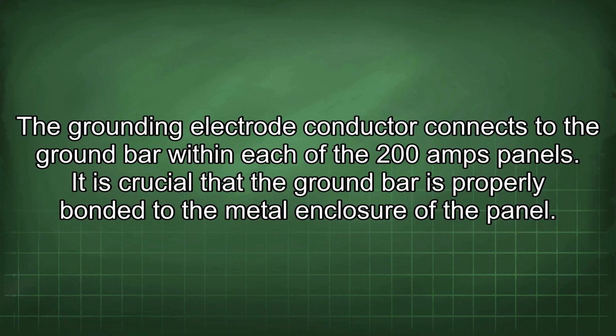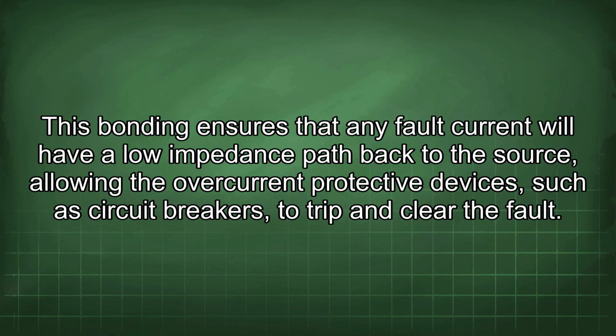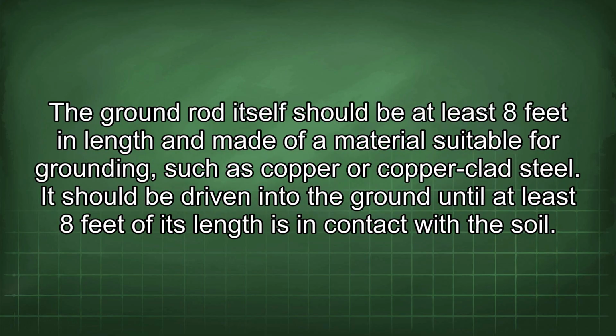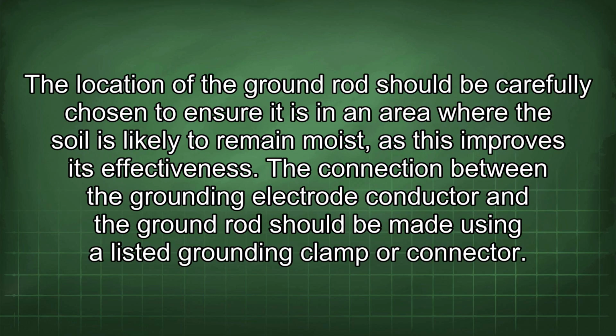It is crucial that the ground bar is properly bonded to the metal enclosure of the panel. This bonding ensures that any fault current will have a low impedance path back to the source, allowing the overcurrent protective devices, such as circuit breakers, to trip and clear the fault. The ground rod itself should be at least 8 feet in length and made of a material suitable for grounding, such as copper or copper-clad steel. It should be driven into the ground until at least 8 feet of its length is in contact with the soil. The location of the ground rod should be carefully chosen to ensure it is in an area where the soil is likely to remain moist, as this improves its effectiveness.